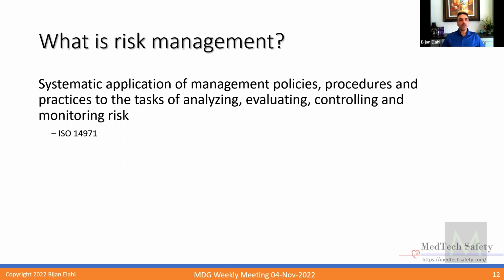Right. So I was talking about how we have 4 tasks: analyzing, evaluating, controlling, and monitoring risks. These are 4 specific activities that ISO 14971 asks for, and they're detailed in the standard as to what they are.